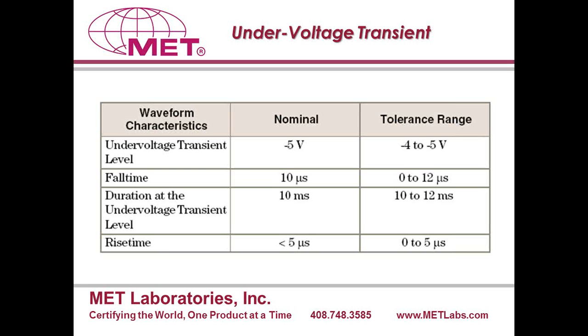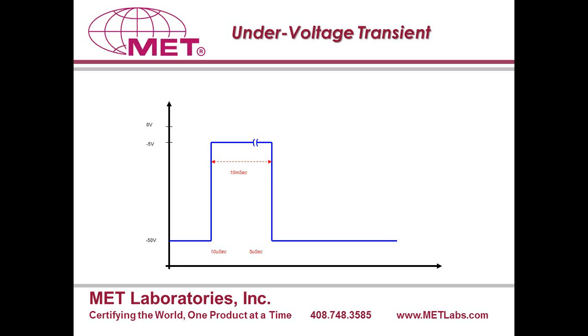So basically, this slide is giving a summary of the undervoltage requirement. Nominal voltage is minus 48 volts. Before I describe that, let me go to my next slide where we can look at the waveform, and I can describe these parameters while we are looking at it. So this waveform is basically showing that we have a minus 50 volt system. The device normally operates at minus 50 volts or 48 volts. The voltage needs to switch from minus 50 volts to minus 5 volts with a rise time of 10 microseconds. It has to stay at minus 5 volts for 10 milliseconds.